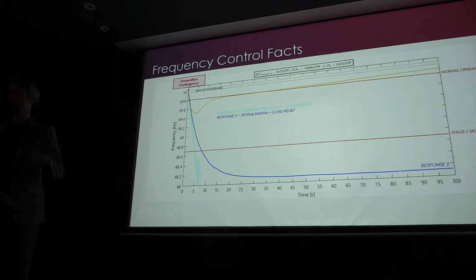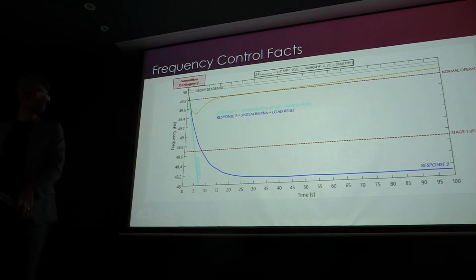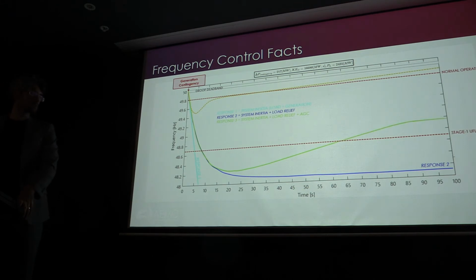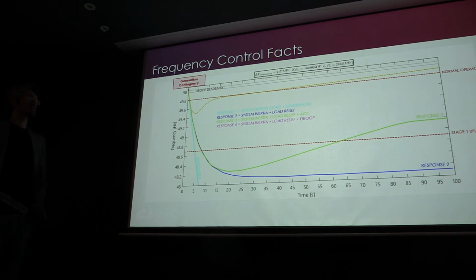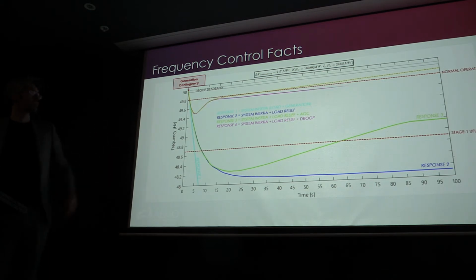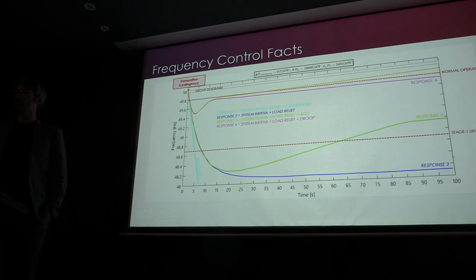That's not enough, so there are other components as well. Just one point: system inertia here includes load inertia and generation inertia. Another component is AGC. Will AGC help? Not so much, because the time constant is high, around 8 to 20 seconds maybe. The next one is droop or spinning reserve. If we add that to the trace, the pink one, we're getting very close.